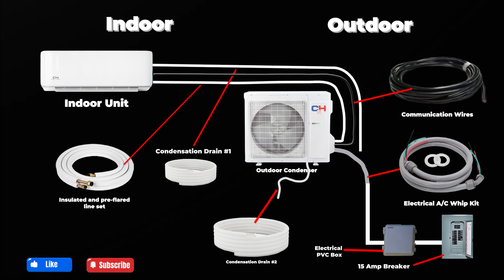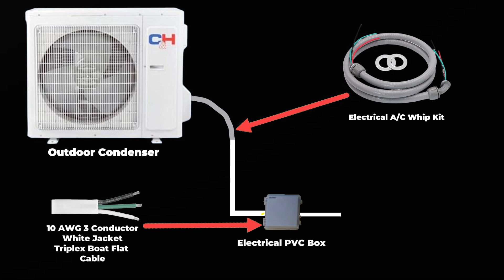Now let's move on to the next stage. This electrical AC whip kit is attached to the electrical PVC box, which contains a 10 AWG 3-conductor white jacket triplex boat flat cable. This cable is routed inside the building and directly connected to the circuit breaker.